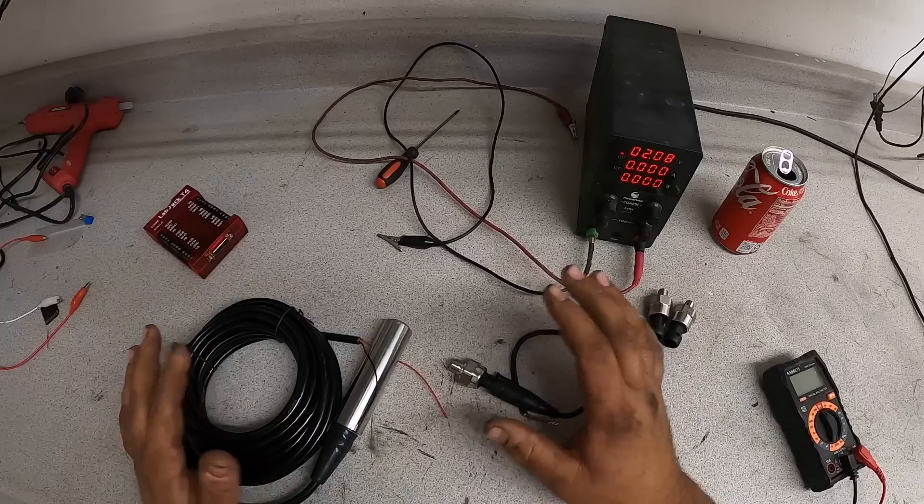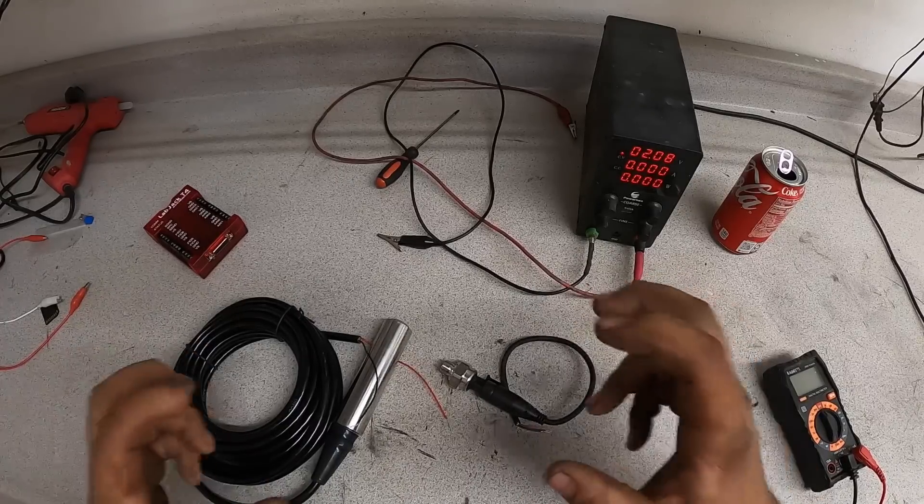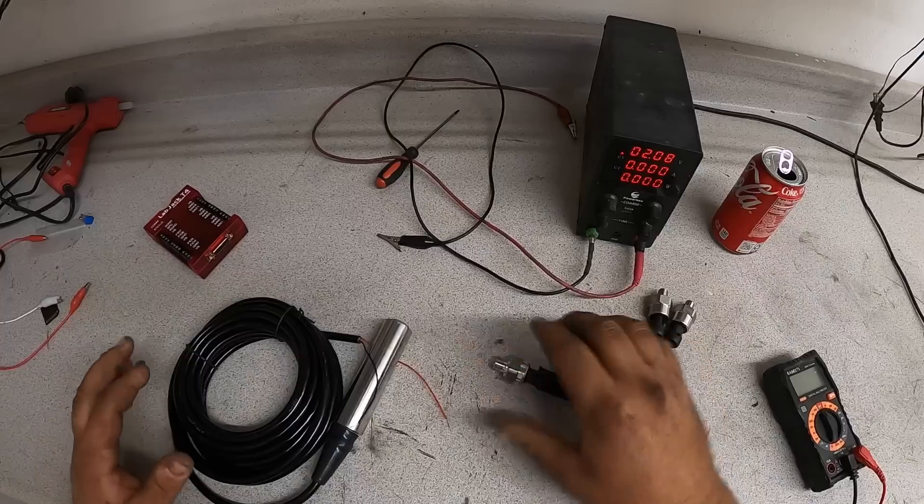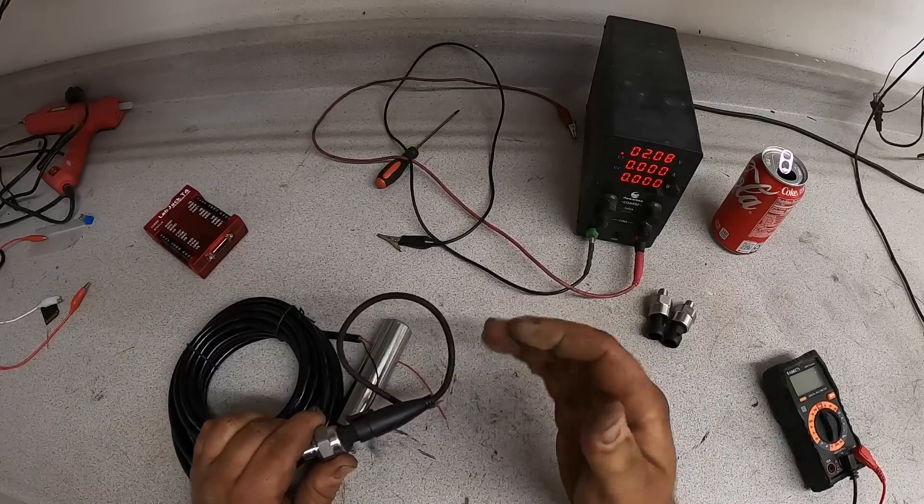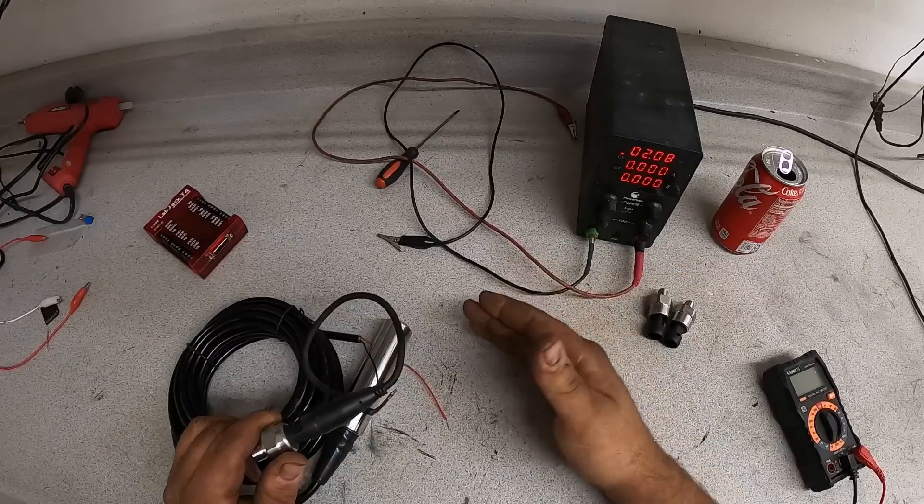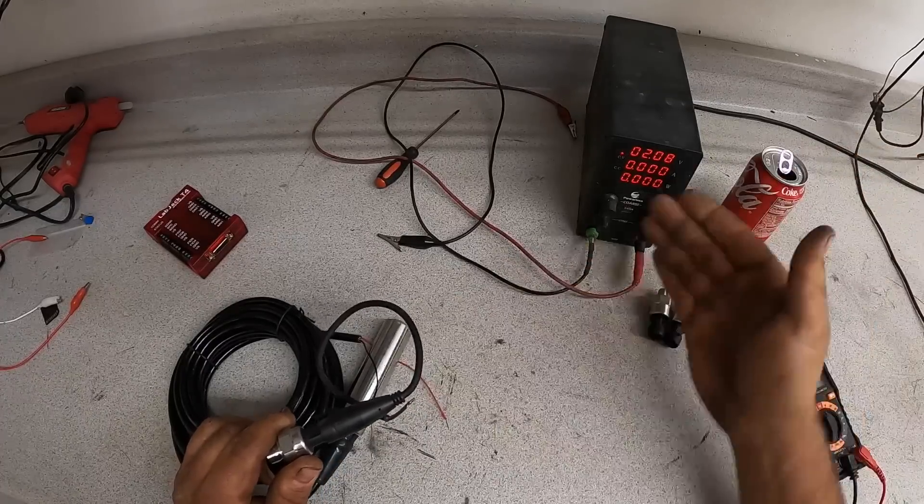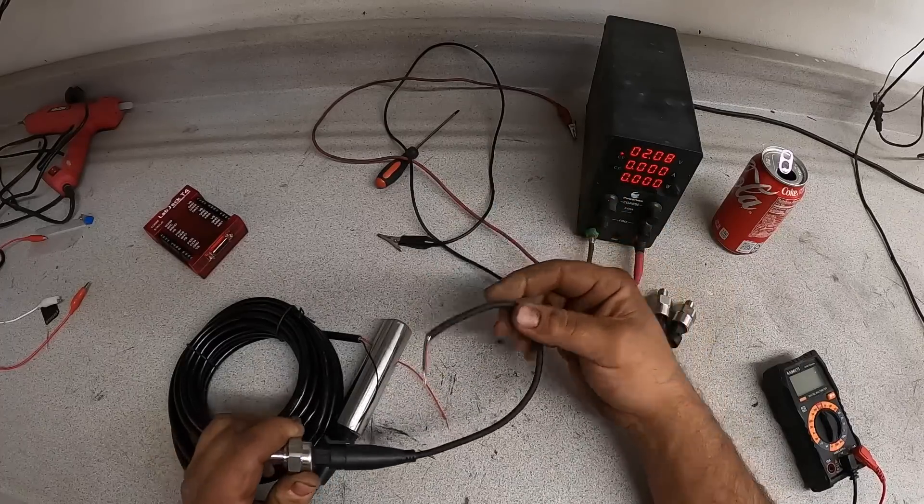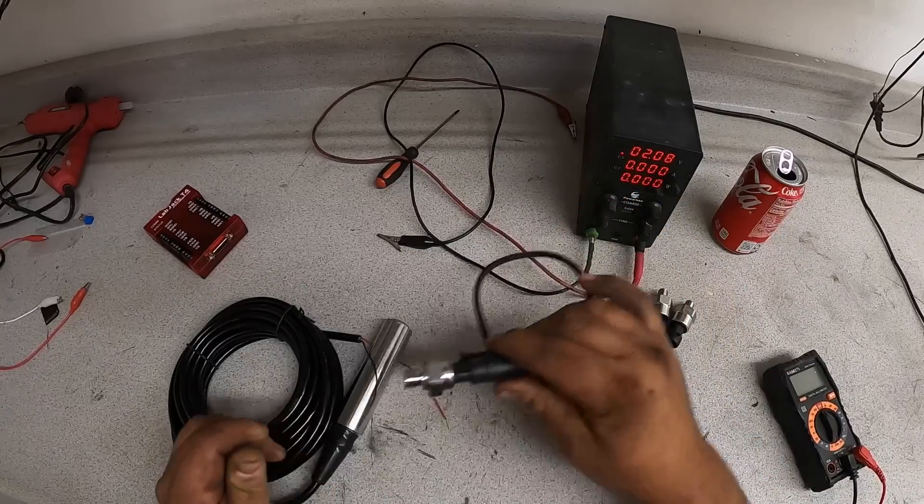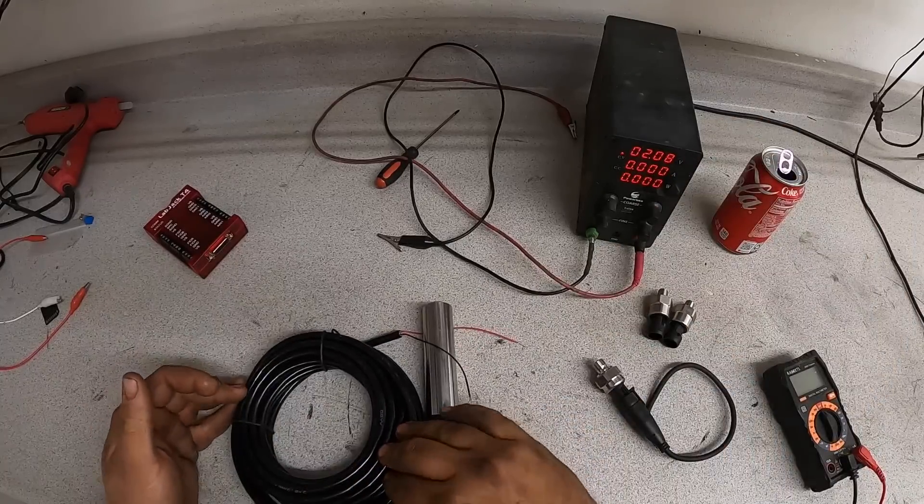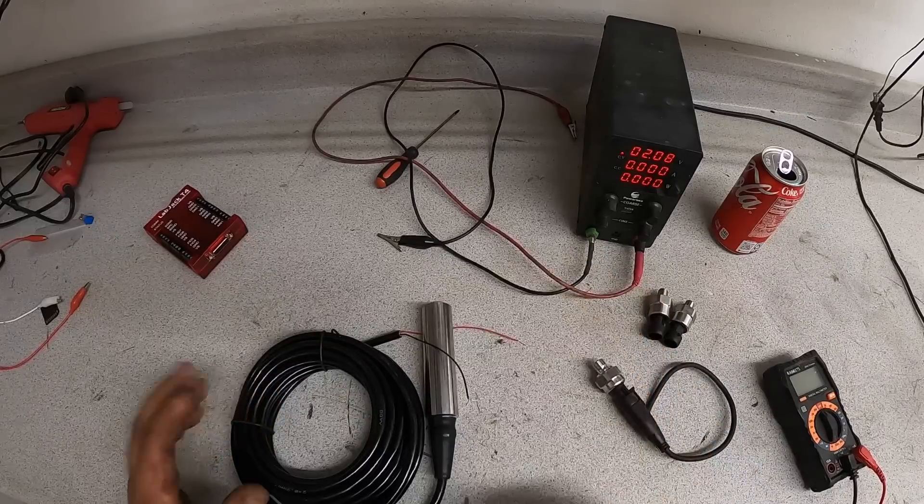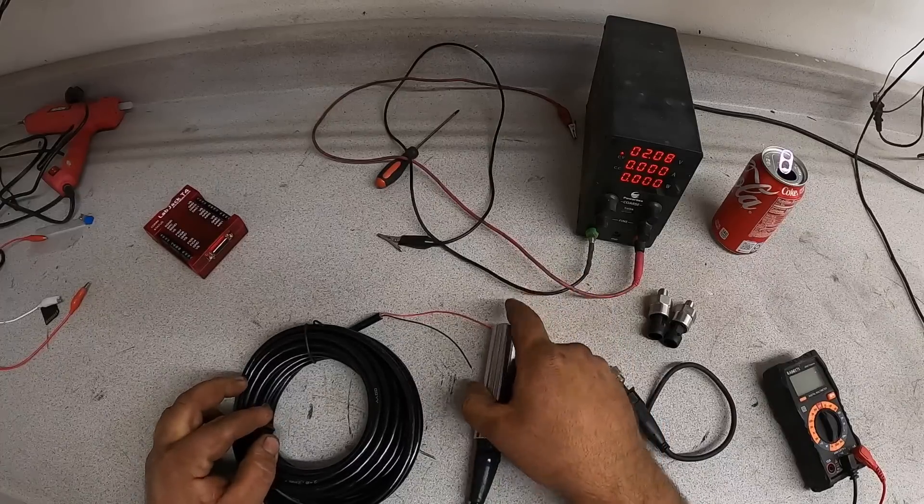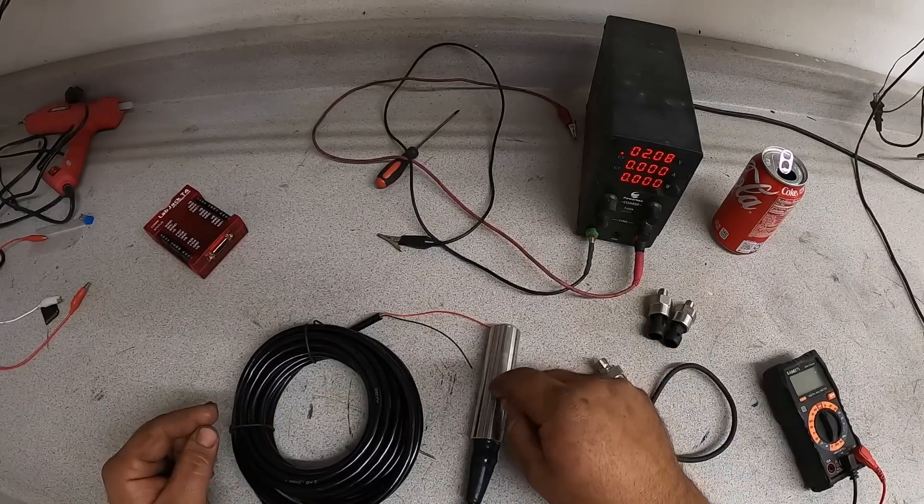So sensors come typically in two different styles of electrical output. They're either zero to five volts, or they are four to 20 milliamps. This means that as the pressure increases, it increases the voltage between typically they would start out at like half of a volt up to four and a half volts. They don't actually go quite zero to five. But it varies the voltage depending on the input, the more pressure, the higher the voltage. Or they come in a four to 20 milliamp, meaning that the higher the pressure or higher the level or higher whatever you're reading, in this case it would be a tank level, it increases the amount of current that can pass through this.